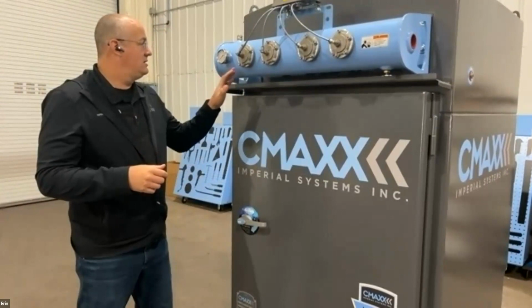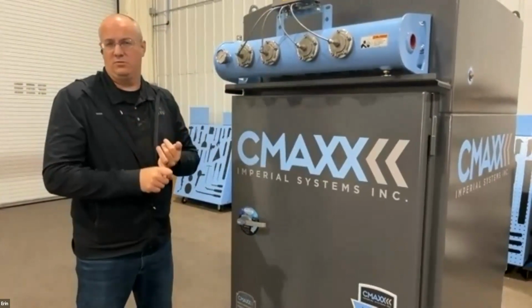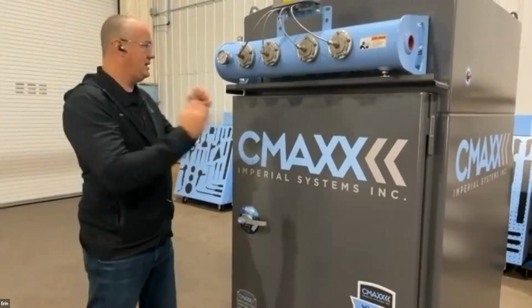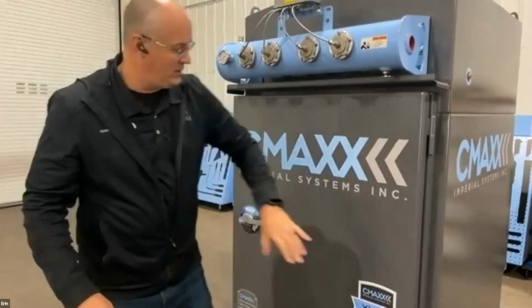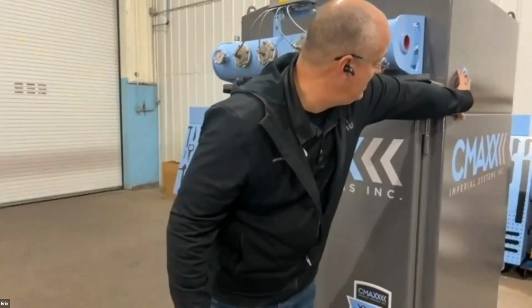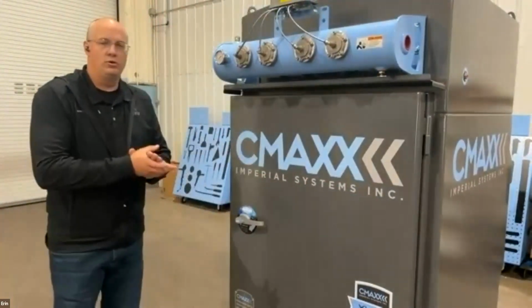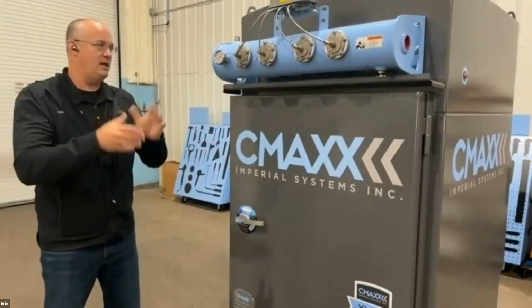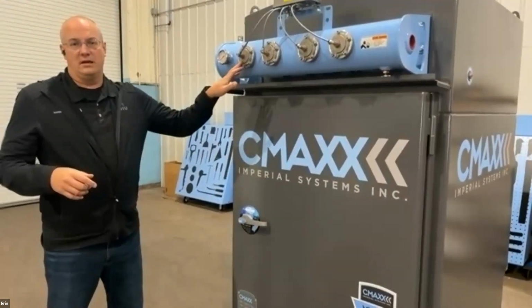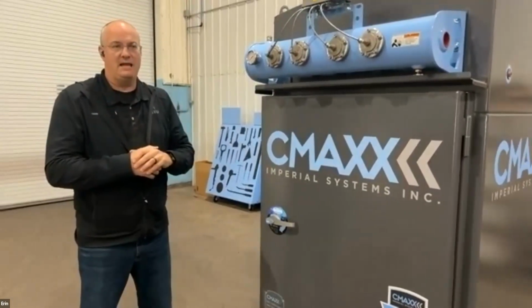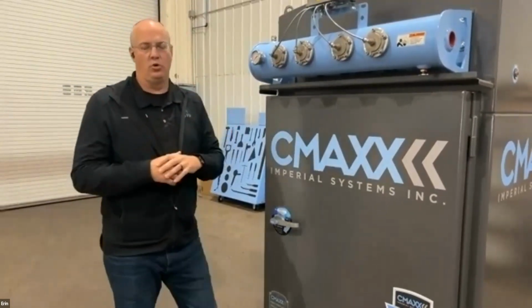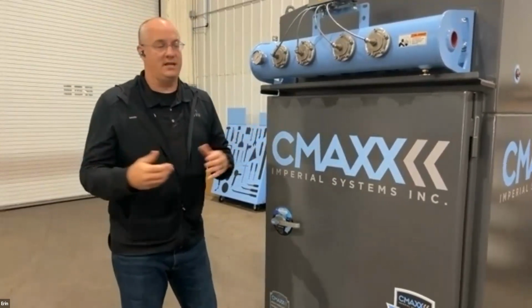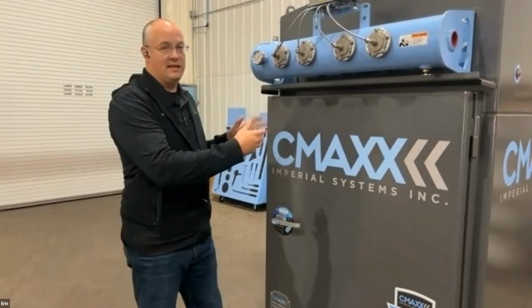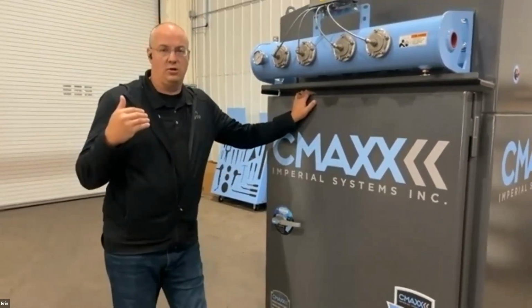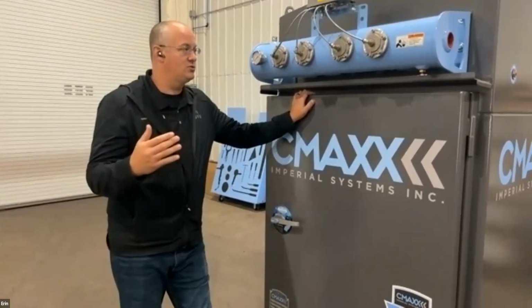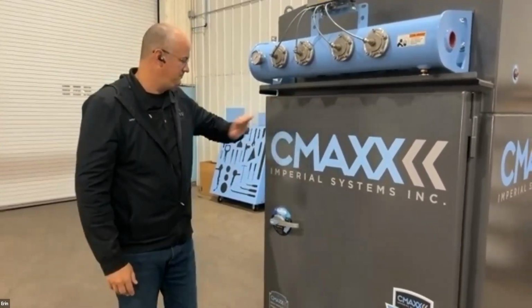These can be designed to clean on demand, which means when the filters get dirty enough, they can clean. They'll clean automatically by measuring the pressure between the dirty side and the clean side. That would be through a timer board that cleans that, and a pressure gauge. You can also clean these what we call downtime cleaning, and that is typically when the shop shuts down or when a piece of equipment they're attached to turns off, and it cleans the filters at that time. It's really good. It just helps keep all the pressures at the right level and cleans whenever it's offline.